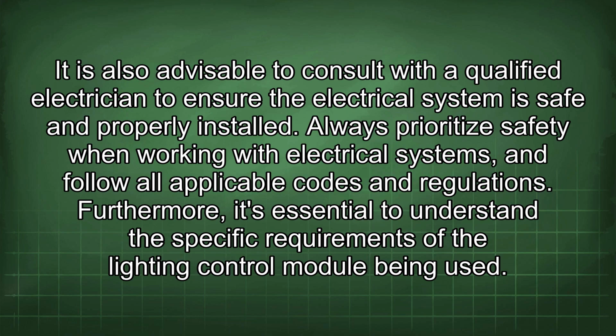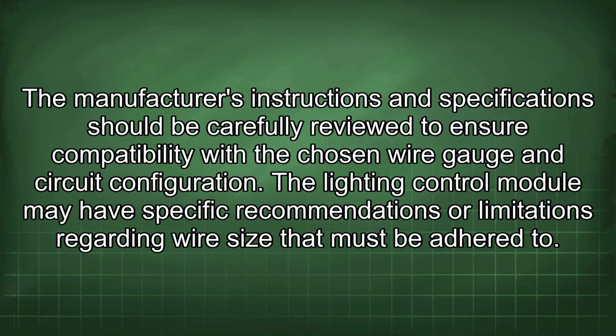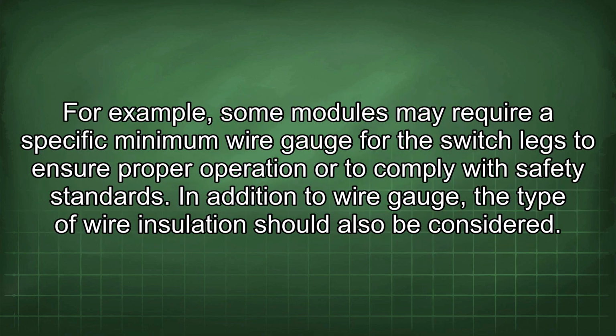Furthermore, it's essential to understand the specific requirements of the lighting control module being used. The manufacturer's instructions and specifications should be carefully reviewed to ensure compatibility with the chosen wire gauge and circuit configuration. The lighting control module may have specific recommendations or limitations regarding wire size that must be adhered to. For example, some modules may require a specific minimum wire gauge for the switch legs to ensure proper operation or to comply with safety standards.